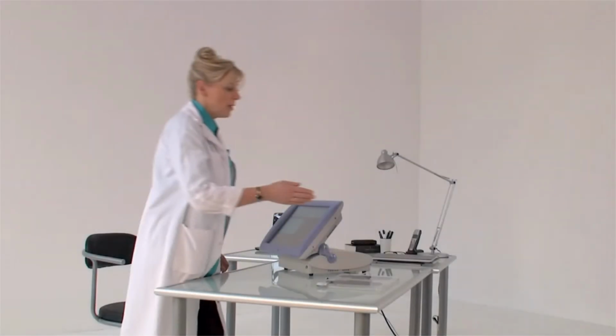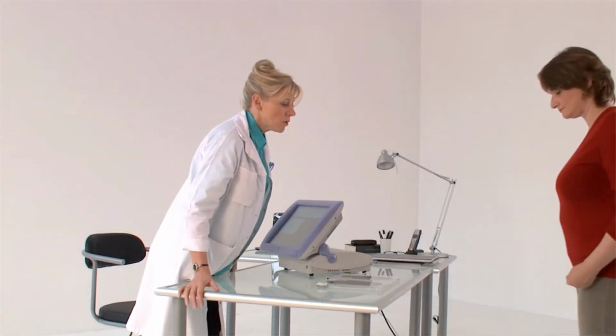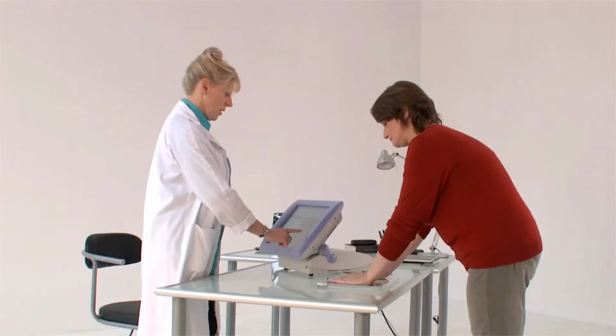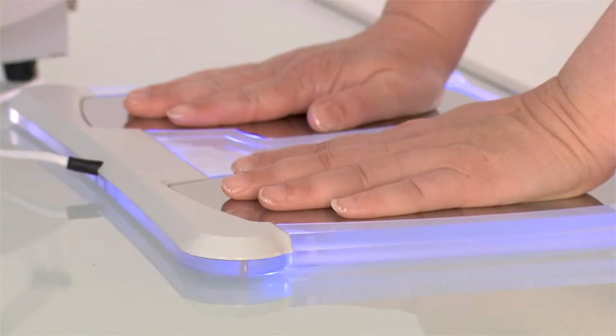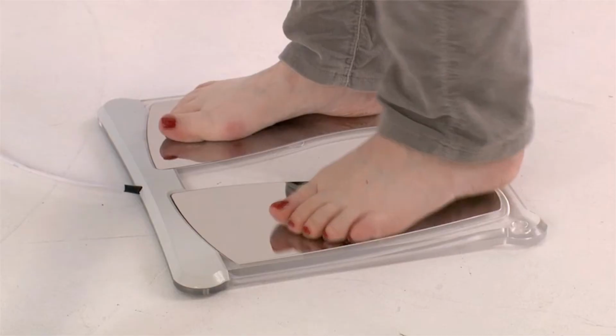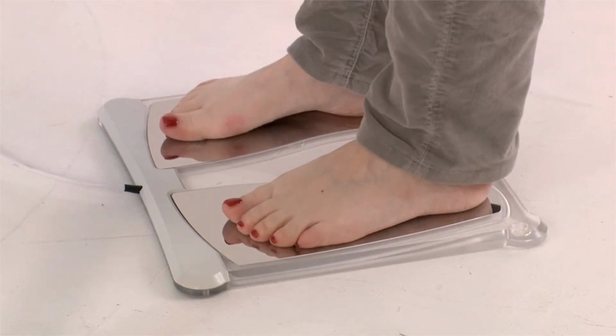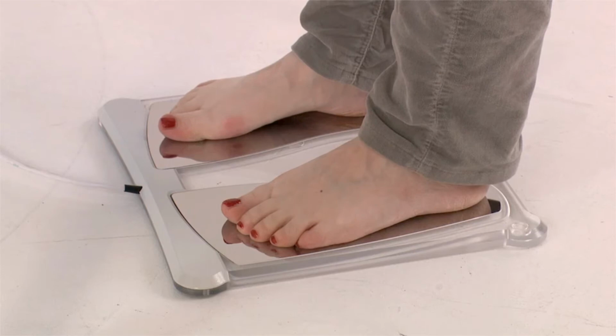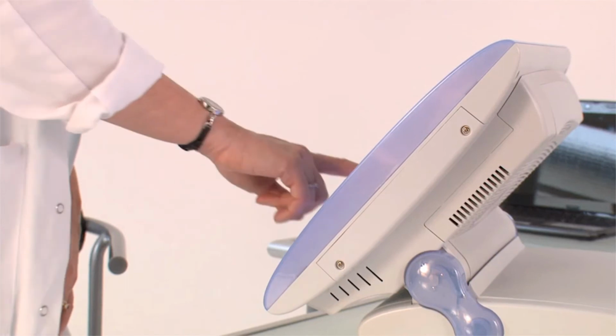The patient is asked to put his hands and feet on the stainless steel electrode plates. They must be centered on the plate for maximum skin-to-electrode contact. Movement must be avoided, and the subject must not be touched during the scan. The patient's name or ID, age, gender, weight, and height are typed into the analyzer. The test starts when the scan button is pressed.